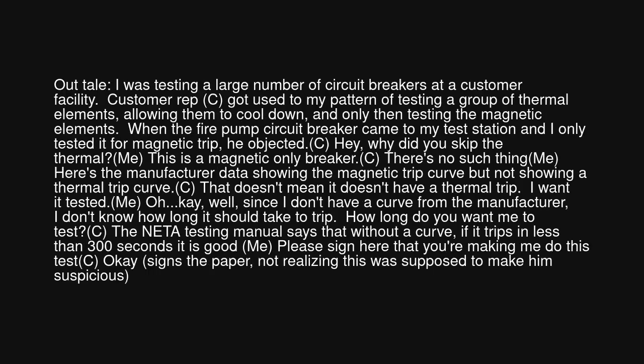NETA. Out tale. I was testing a large number of circuit breakers at a customer facility. Customer rep, C, got used to my pattern of testing a group of thermal elements, allowing them to cool down, and only then testing the magnetic elements. When the fire pump circuit breaker came to my test station and I only tested it for magnetic trip, he objected. C: Hey, why did you skip the thermal? Me: This is a magnetic-only breaker. C: There's no such thing. Me: Here's the manufacturer data showing the magnetic trip curve but not showing a thermal trip curve.